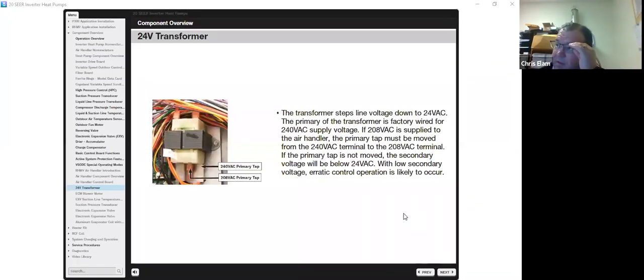Okay, another component of the air handler has a 24 volt step down transformer. The primary of the transformer is wired for 240 volts. If 208 volts is supplied, the primary tap must be moved from 240 to 208. If the primary tap is not moved, the secondary voltage will be below 24 volts AC. Low voltage, erratic control is likely to occur.